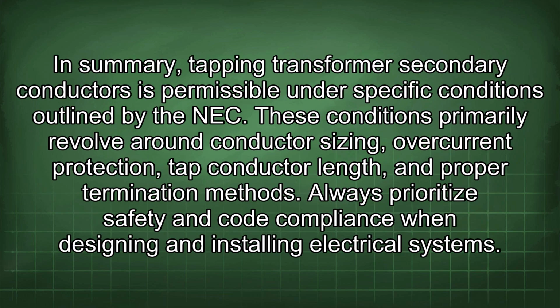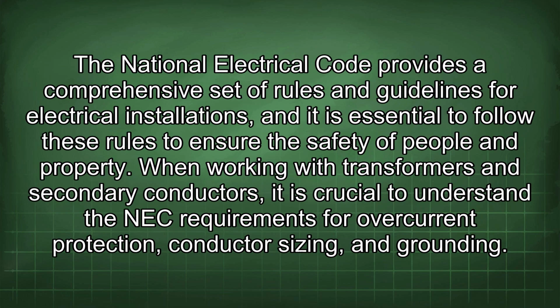In summary, tapping transformer secondary conductors is permissible under specific conditions outlined by the NEC. These conditions primarily revolve around conductor sizing, overcurrent protection, tap conductor length, and proper termination methods. Always prioritize safety and code compliance when designing and installing electrical systems. The National Electrical Code provides a comprehensive set of rules and guidelines for electrical installations, and it is essential to follow these rules to ensure the safety of people and property.